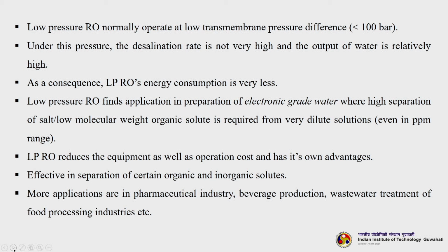Now, low pressure RO normally operates at low transmembrane pressure, less than 100 bar. Under this pressure the desalination rate is not very high, however, the output of water is large. As a consequence, low pressure RO's energy consumption is very less. Low pressure RO finds application in preparation of electronic grade water, which is used in electronics industries, where high separation of salt and low molecular weight organic solute is required from very dilute solutions, even in ppm range.